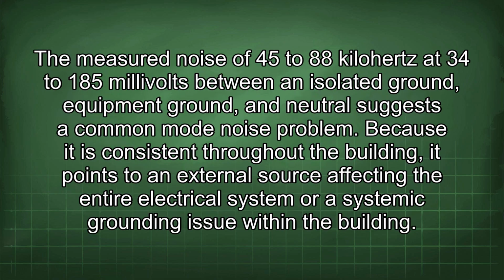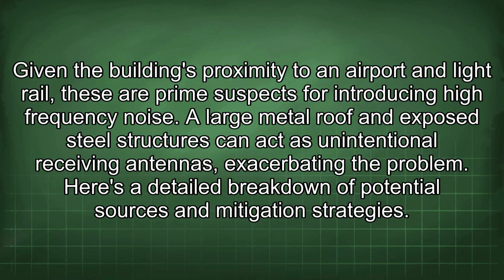The measured noise of 45 to 88 kHz at 34 to 185 mV between an isolated equipment ground and neutral suggests a common mode noise problem. Because it is consistent throughout the building, it points to an external source affecting the entire electrical system or a systemic grounding issue within the building. Given the building's proximity to an airport and light rail, these are prime suspects for introducing high-frequency noise. A large metal roof and exposed steel structures can act as unintentional receiving antennas, exacerbating the problem. Here's a detailed breakdown of potential sources and mitigation strategies.